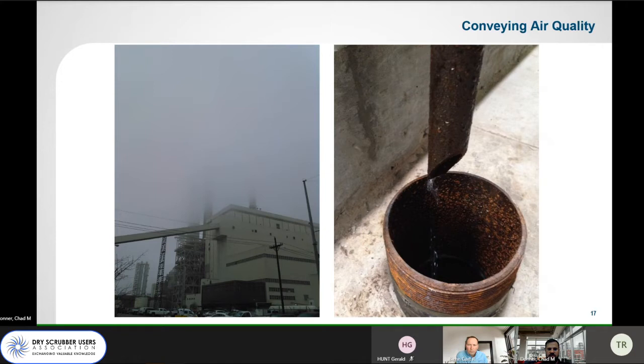The picture on the left is what the sky looked like outside, and the picture on the right is the condensate drain off of the dryer. So that's the amount. We're basically pouring a continuous stream of moisture out of the conveying air that would have been conveyed with the hydrated lime, causing scaling and pluggage potential had we not had the drying system installed.